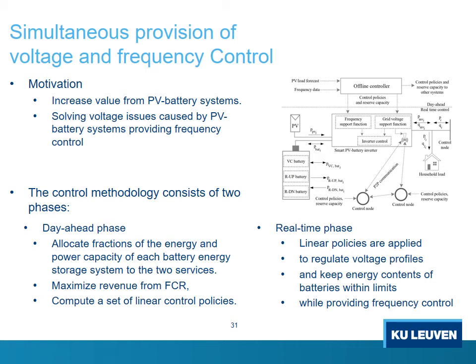There is another motivation behind combining voltage control with frequency control. That is, providing frequency control with photovoltaic battery systems connected to the low voltage distribution grid can lead to voltage issues. In order to mitigate these issues, part of the reserve capacity of the photovoltaic battery systems should be dedicated to solving voltage problems caused by their services. In my opinion, grid operators should require frequency control providers with photovoltaic battery systems located in the distribution network to provide frequency control simultaneously with voltage control.